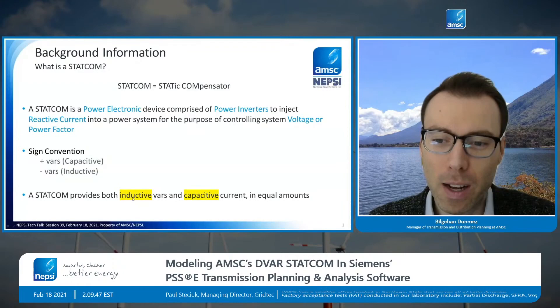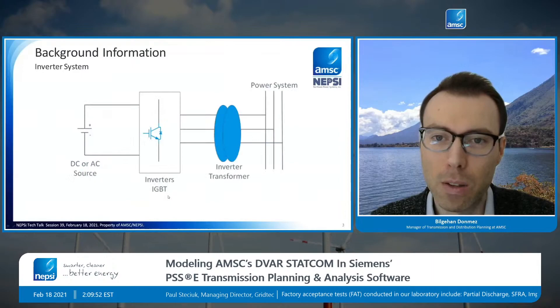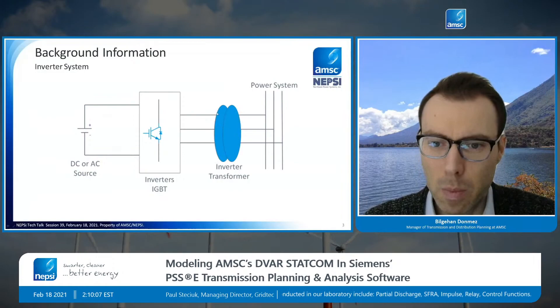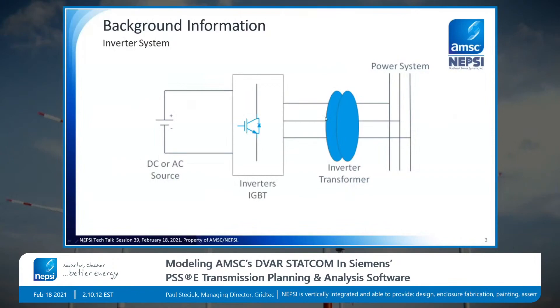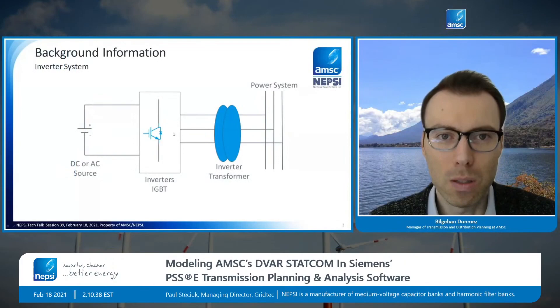The STATCOM provides both inductive and capacitive current. The inverter system connects to the system with a step-up transformer. The terminals of the STATCOM are at 480 volts, and then we step it up to medium voltage, typically anywhere from 12 kV to 35 kV. From there, there could be another transformation up to the transmission system. On the low side of the step-up transformer, we have IGBTs and a DC capacitor as a DC source, which is rectified to generate an AC waveform using these inverters.